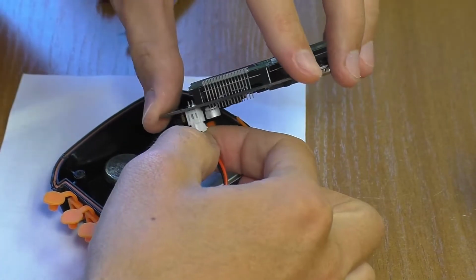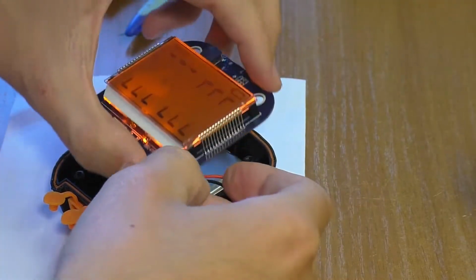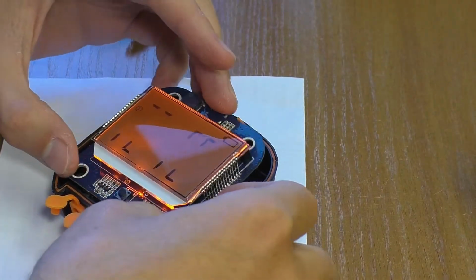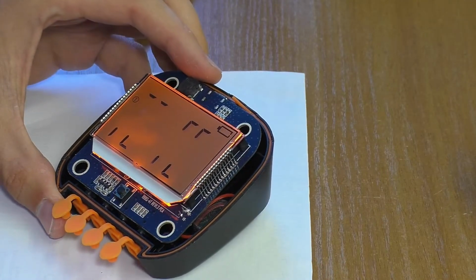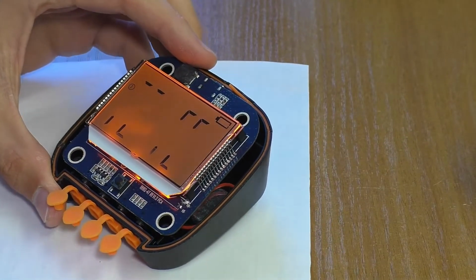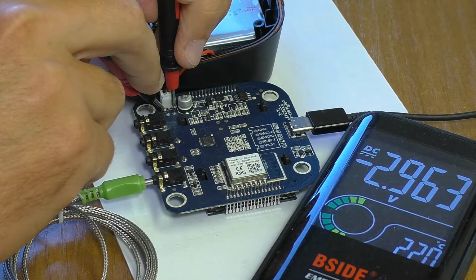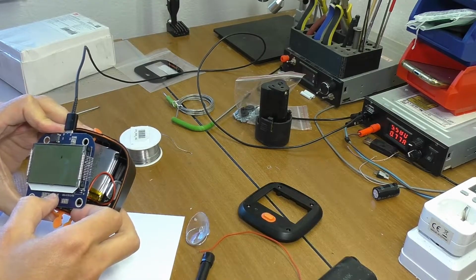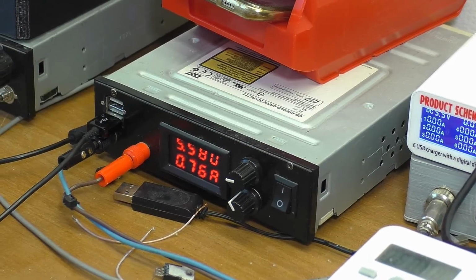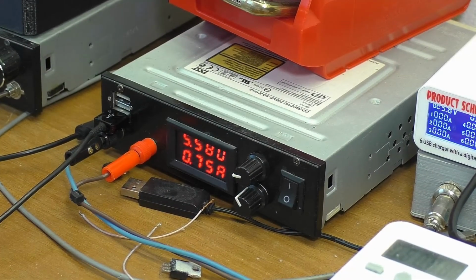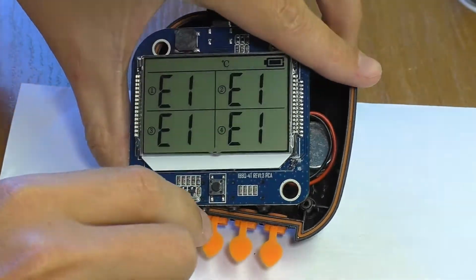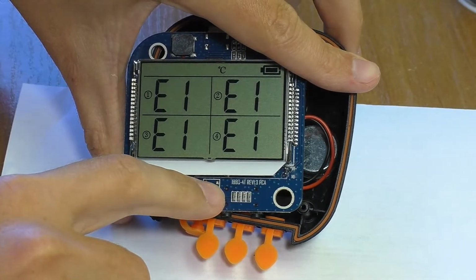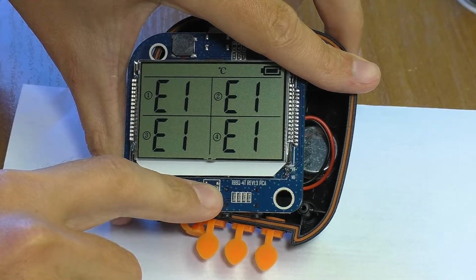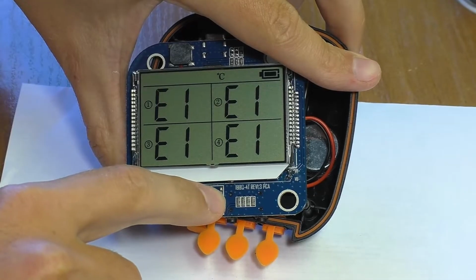Well, let's see how the device behaves now. I connect the battery, the thermometer turns on the screen, with some incomprehensible symbols. Obviously, the battery is discharged. The voltage on it is less than 3 volts. I connect it to charging. The charging current is good, about 800 milliamps. After some time, the battery is well charged. The device gives a value of E1 on all channels of the temperature sensors. Again, there is no response to pressing the power button.